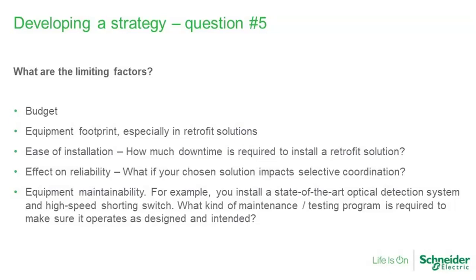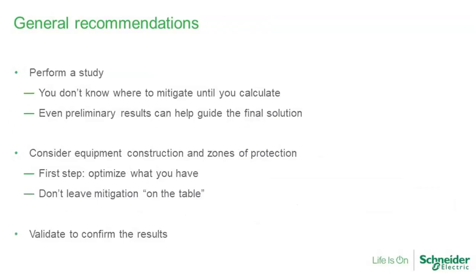Equipment maintainability can even be an example. You install a state-of-the-art optical detection system and high-speed shorting switch. What kind of maintenance or testing program is required to make sure it operates as it's designed and intended? If you have to test it every 2 years and you're in a facility where you only have maintenance shutdowns every 4 years, that's something you ought to think about before you move down that path. And I'm closing in on the end here. Just a couple of general recommendations.